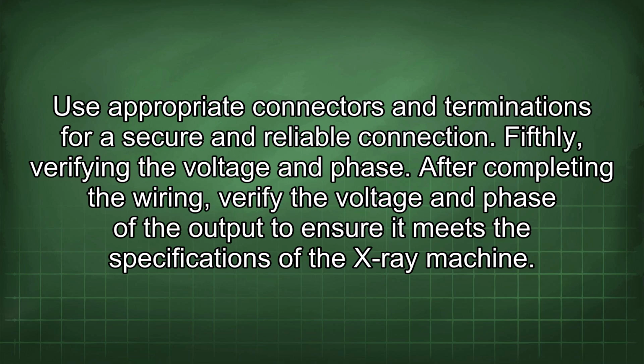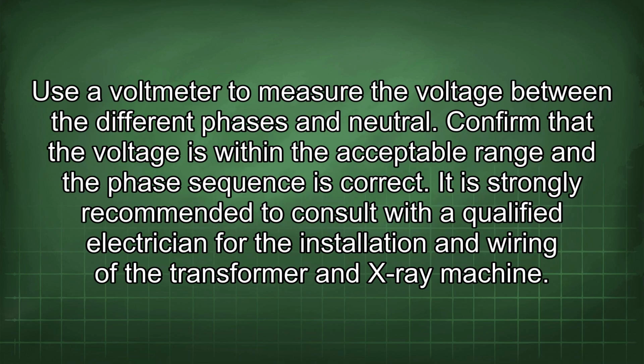Fifthly, verifying the voltage and phase. After completing the wiring, verify the voltage and phase of the output to ensure it meets the specifications of the X-ray machine. Use a voltmeter to measure the voltage between the different phases and neutral. Confirm that the voltage is within the acceptable range and the phase sequence is correct.